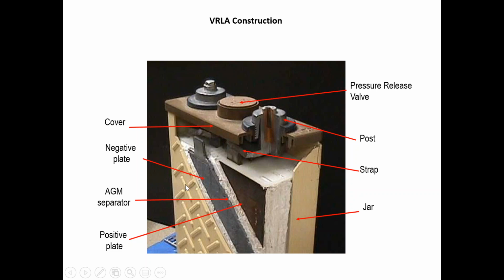But again, opaque jars, you can't see into them. Instead of a flame arrestor where you would add water or sample electrolyte, it's a pressure relief valve. That valve itself is fixed into the jar, and it's not meant for periodic removal for anything. That's where the term sealed comes into place. And these valves typically release around 3 to 5 psi depending on the manufacturer. So if these batteries see high temperature, high heat, anything that would cause positive pressure inside, so the cell itself won't rupture or blow apart, there's a valve that'll reseat after pressure release.